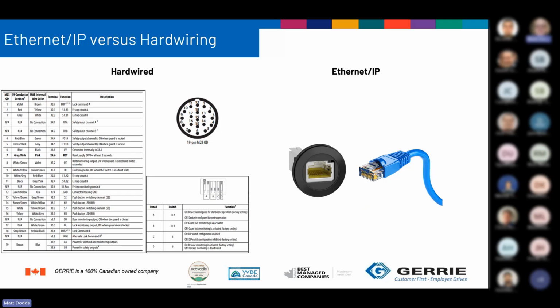In my experience, I worked at a company and they had put in the hardwired one, and they said, "Oh yeah, can we add door monitoring to that?" Oh, we didn't run enough wires. We ran like a 16 pin cable or a 16 wire cable, so they would have to re-pull all the wires. Well, with Ethernet, everything's there. So if you're going to look at this solution, highly recommend the Ethernet IP version.